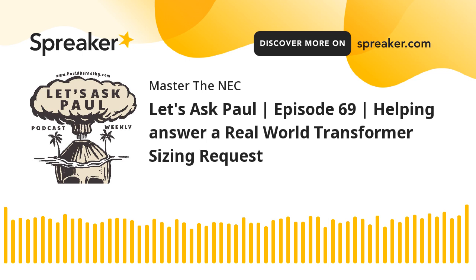For example, we're starting out here at a minimum of a 30 kVA, but I believe to handle 100 amps, you probably are going to have to jump up to a 45 kVA, because three-phase transformers kind of jump in size. Once you get to 30, it goes 15 kVA, 30 kVA, then it jumps to 45 kVA for those 480 to 208 volt transformers, three-phase.